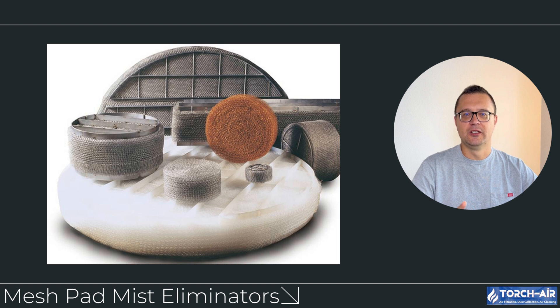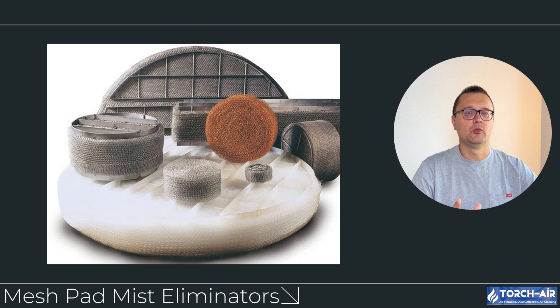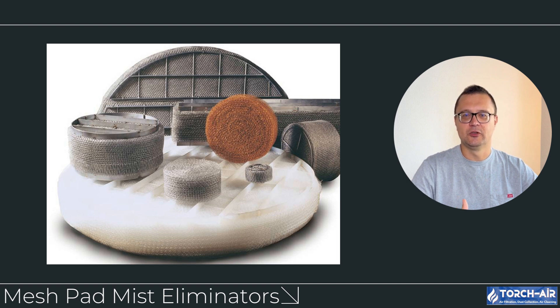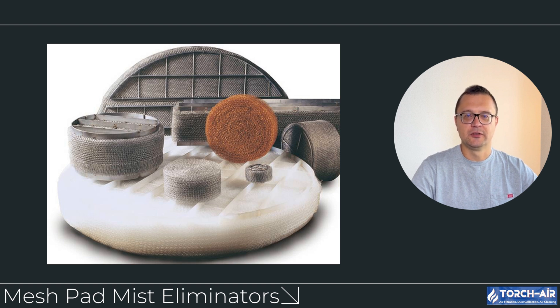There are several types of mist eliminators and droplet separators, each designed to handle different mist or droplet sizes, gas flow rates, and applications. The first type is mesh pad mist eliminators. These consist of woven or knitted mesh materials that create a high surface area for droplets to collide with. As the gas stream passes through the mesh, mist droplets are captured and coalesce into larger droplets that fall out of the stream. Best for fine mist and small droplet sizes, typically below 10 microns. Mesh pads are efficient at removing fine mist and aerosols, but they can become clogged with particulates over time and may require regular cleaning or replacement, especially in dusty environments.